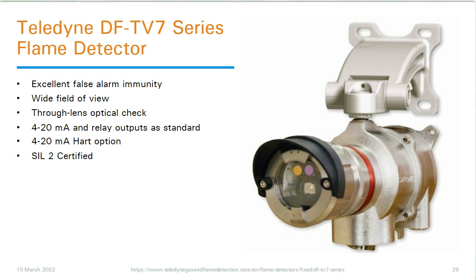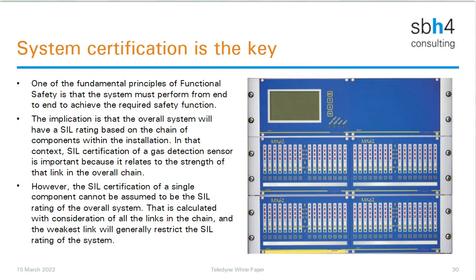And when we think of those elements of the gas and flame detection system, fixed gas detectors, flame detection systems, when we think about those pieces of hardware, they're all often connected into a very, very sophisticated gas and flame detection system across a storage tank terminal, LNG facility or a refinery, whatever the system might be, whatever the operation might be. So a lot of data and information is coming into a controller, such as the one shown here, the MX62. And again, the software that lives inside these kinds of controllers themselves are also an integral part of the overall system. And certification for these controllers is also critical to make sure that the overall system is at an appropriate safety integrity level.